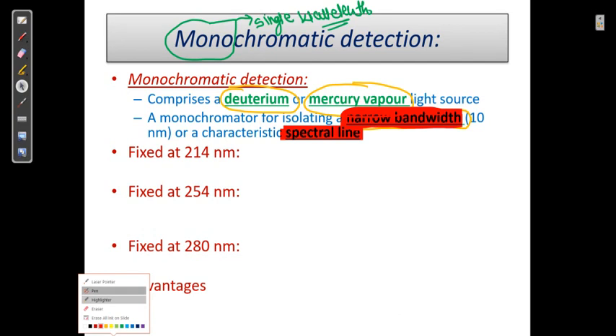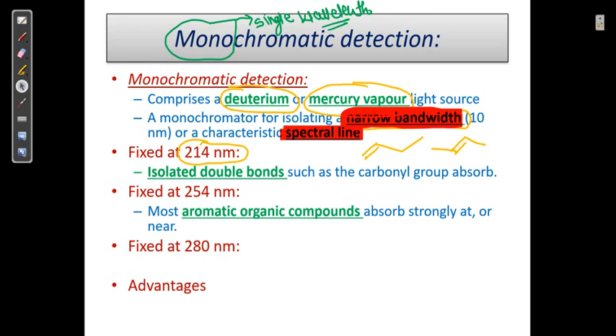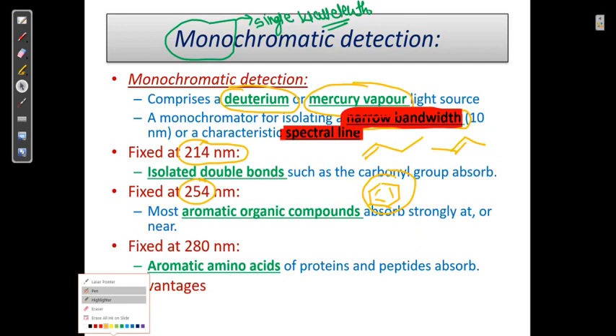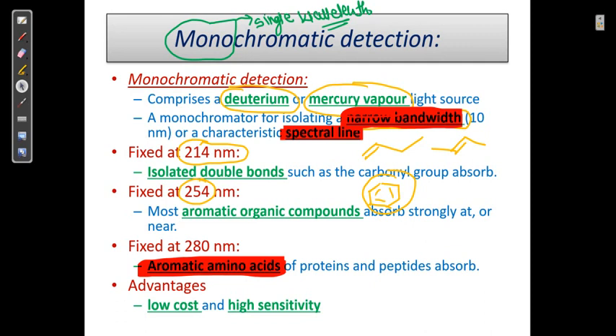The detector can be fixed at 214 nm, which detects isolated double bonds. At 280 nm, aromatic amino acids are detected. Monochromatic detection is low cost and offers high sensitivity.